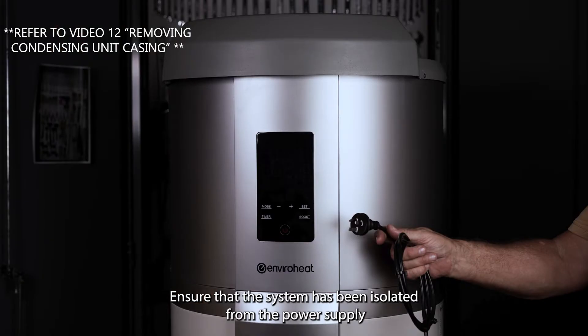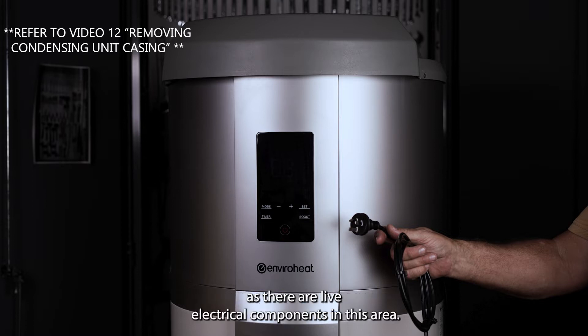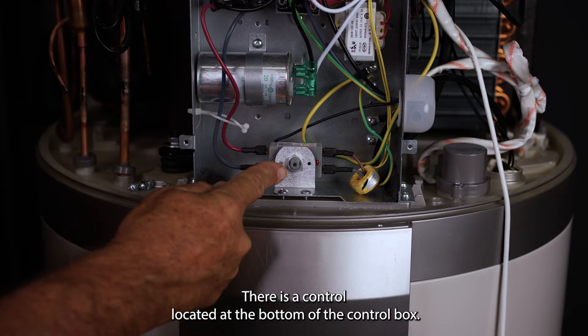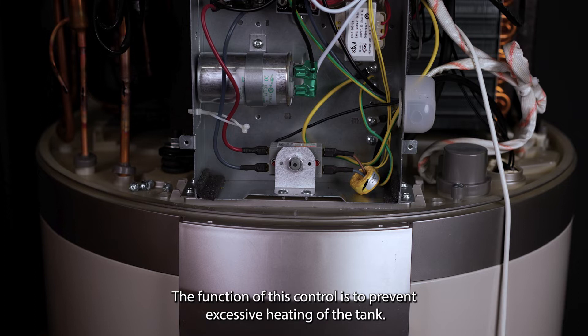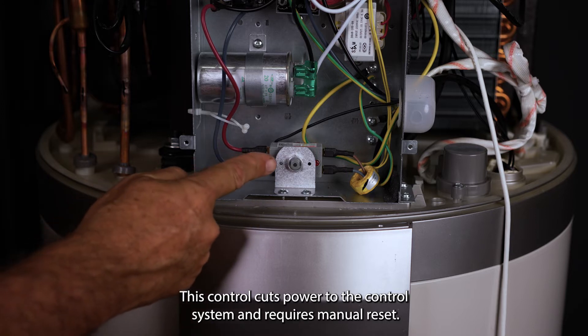Ensure that the system has been isolated from the power supply as there are live electrical components in this area. There is a control located at the bottom of the control box. The function of this control is to prevent excessive heating of the tank. This control cuts power to the control system and requires manual reset.